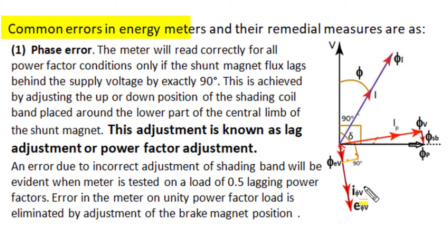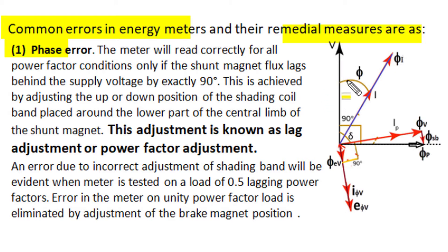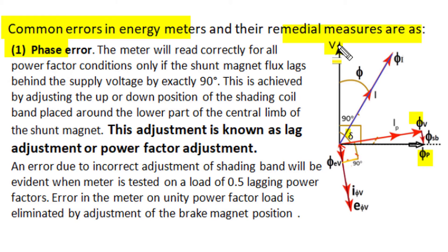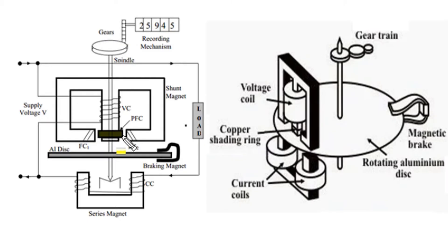The first common error in energy meter measurement is called phase error. The meter must read correctly for all operating power factor conditions. A correctly designed energy meter can read correct values of energy for all power factor conditions only when the flux produced by the shunt magnet lags exactly 90 degrees to the voltage excitation. Practically, due to resistance in the shunt magnet coil and iron losses in its core, the flux lags voltage by an angle delta slightly less than 90 degrees. This is corrected using a shading band — a thick copper conductor loop wound on the central core of the shunt magnet.